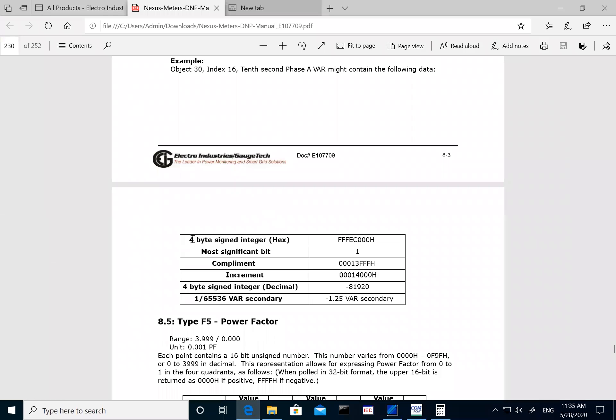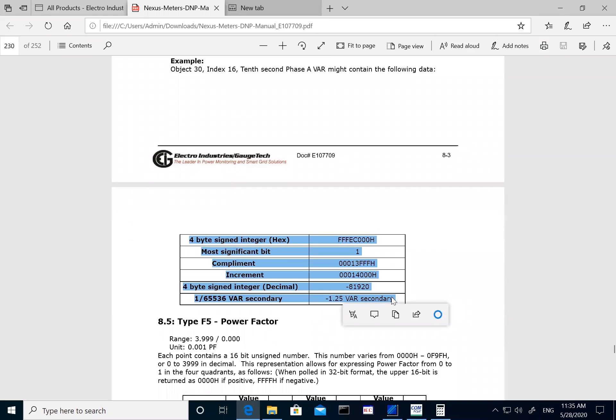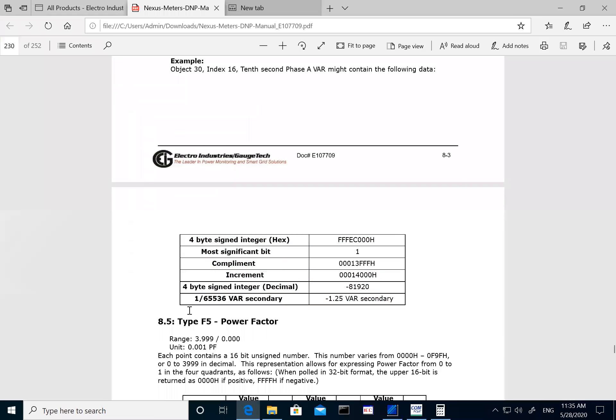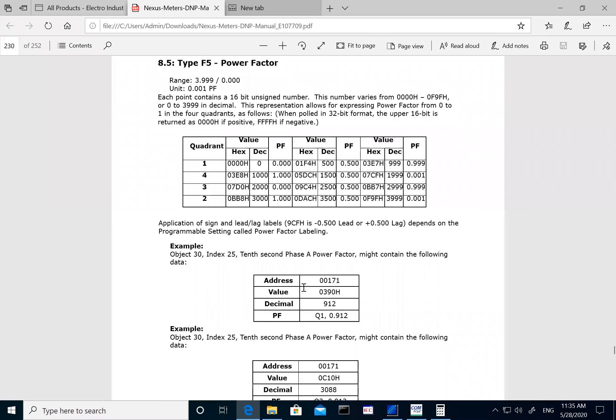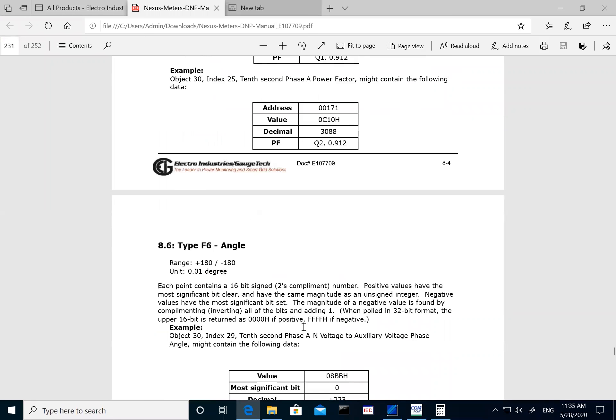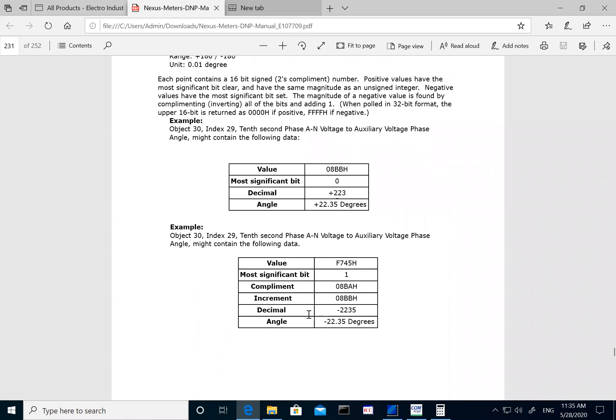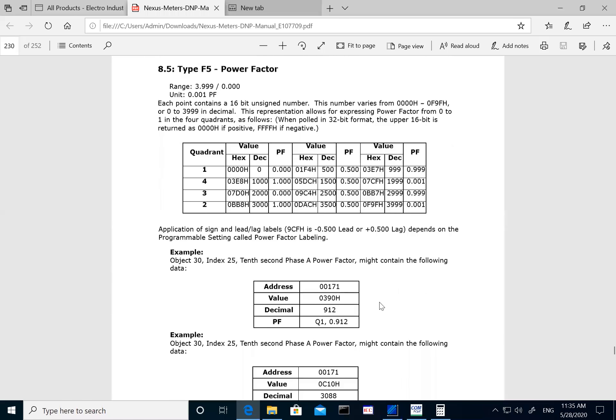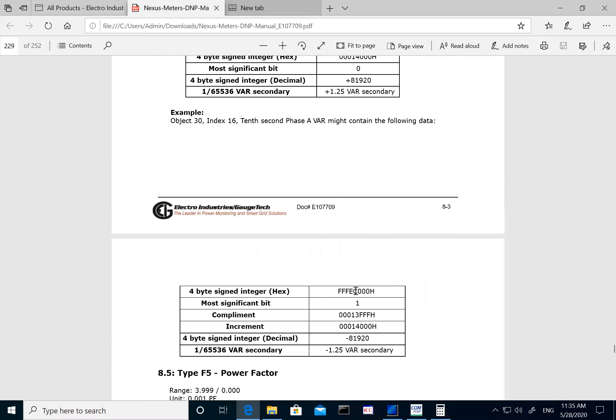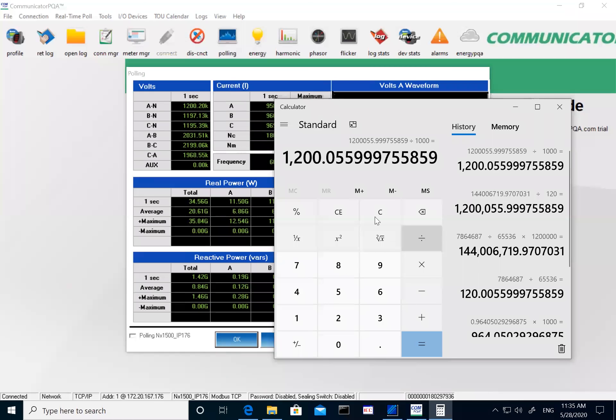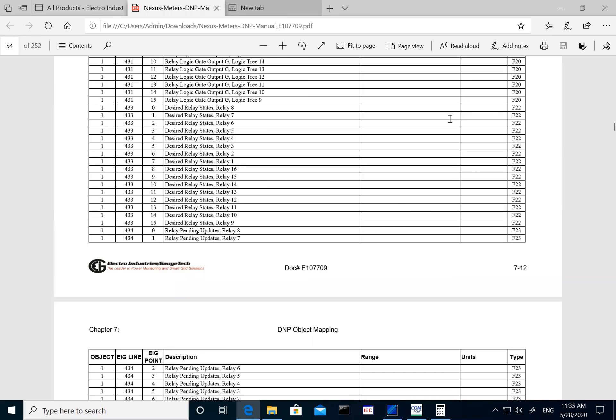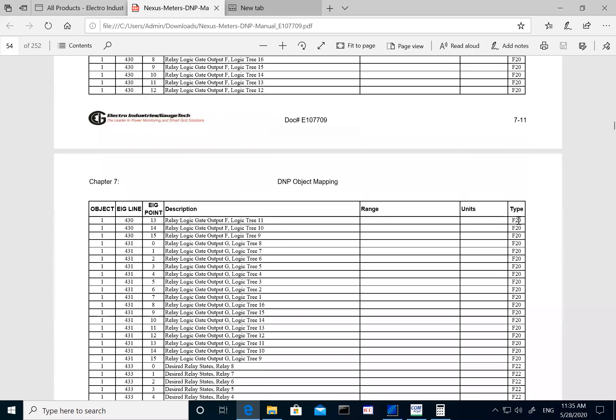It's important to go through the examples in the manual because each parameter can have different math depending on what it's reading. For example, power factor has a different calculation since it's a four-quadrant meter, and phase angle could be a different data type. That's why we show these examples in detail — each value type is listed per line and you can refer to the data type example at the bottom of the manual.